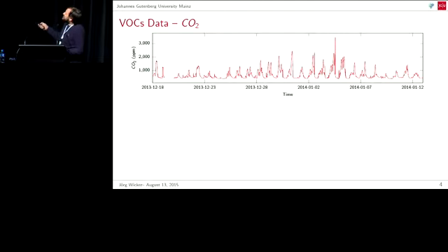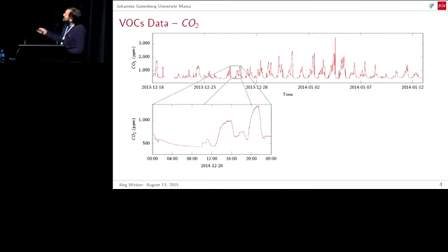If you look at it in more detail, I zoom into this day, the 26th of December. What you see here is basically already the movies. One movie was running here, another one here, another one here, and here's part of another one. Here nothing is going on. There was a movie from the previous day. The concentration of CO2 is high, then it goes down because no one is inside and it gets sucked out.